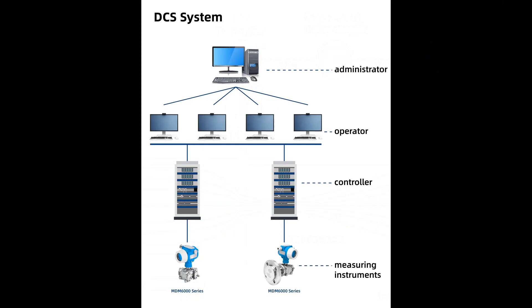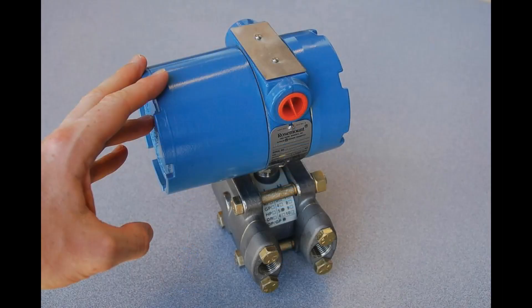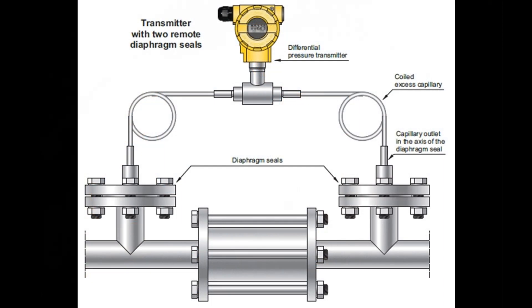In summary, a DP transmitter measures differential pressure by comparing the pressures at two points in a fluid carrying system, typically upstream and downstream of a flow restricting element. The transmitter then converts this differential pressure into an electric signal, often with optional square root extraction and compensation features for accurate flow measurement.